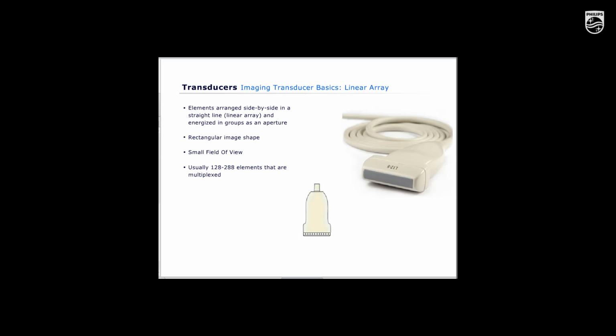The elements in a linear array transducer are rectangular in shape and arranged side by side in a straight line. Applying voltage pulses to a group of elements produces each segment of the beam. In this illustration, a voltage pulse is applied to a group of elements at the same time. For example, elements 1 through 6 will fire, then 2 through 7, then 3 through 8, and so on, until the end of the array is reached. In an actual transducer, this process repeats several times per second. The speed of the illustration is much slower by design, so you can see how the beam forms. Notice that the field of view is rectangular in shape with a flat top.